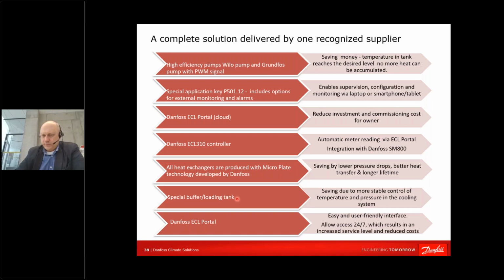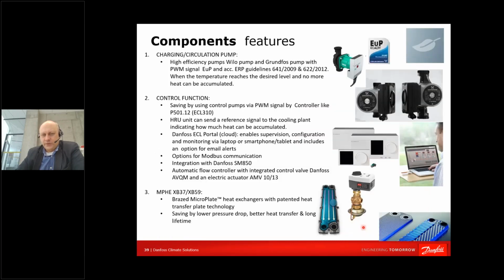Special buffer tanks. Our buffer tanks are specially designed with specific inserts inside, which are enabling water to be loaded and charged without any short circuits in the water flow. So it's very nicely charging. And then for ECL Portal, of course, it's 24/7 easy access to the application. Components we're using, yes, they were just mentioned. Best pumps, ECL, our programs and SCADA units, and models of the heat exchangers, which are made of, as you can see, dimple or microplate pattern, which is allowing the heat exchanger to be more effective compared to the ordinary fishbone pattern.